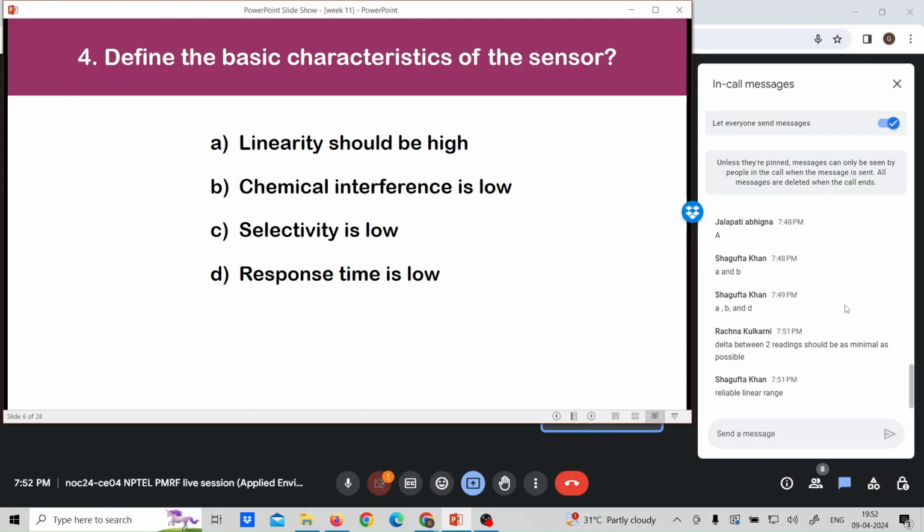as consistent as possible. Ideally, we don't get perfect answers with sensors, or with any instrument basically. There can be room for errors, but that should fall within a range. So that is what we define as linearity, where we ensure some consistency across all the measurements that we have made within a range.